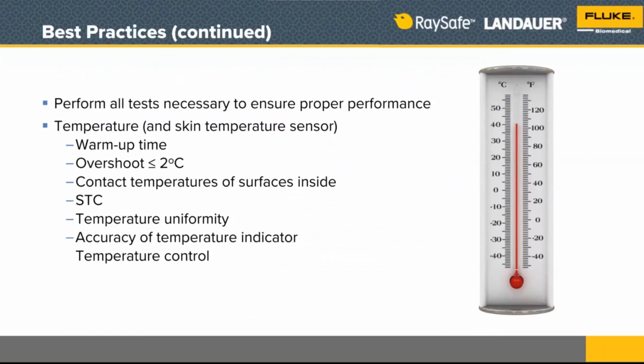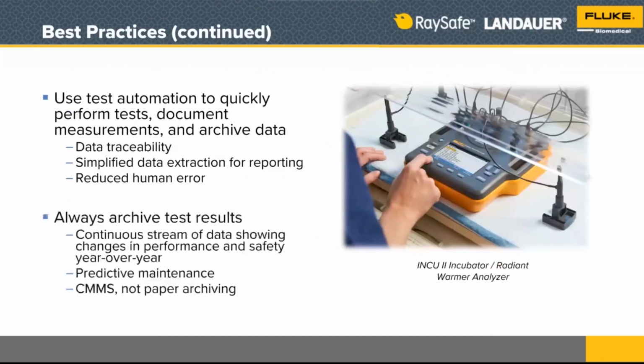So we were talking about automating testing. Always archive your test results. So my recommendation is you archive them electronically. You need to be able to get them into your database, which is where you're going to be able to best look at your failure rates. Your failure rates are important for predicting when you need to make replacements of components and subassemblies. So make sure you're tracking your failure rates. It's not just about passing the tests. It's also about what those failures are and keeping a look at those.